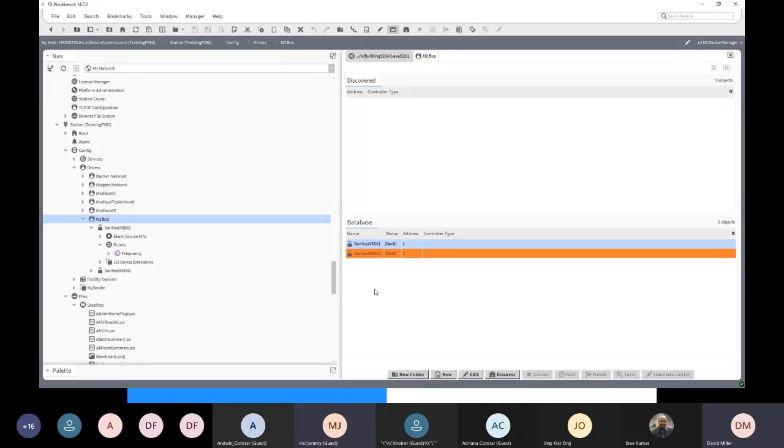But actually, my concern is if I migrate to FX80, what it means is when I discover the FXPCG, but I cannot make it online, is there any way to troubleshoot? Is it a connection problem or the PCG a problem, using the workbench? You got my question? Because previously I just changed the device address and it was successfully online. So I'm not sure if it is the device problem or the workbench communication problem.